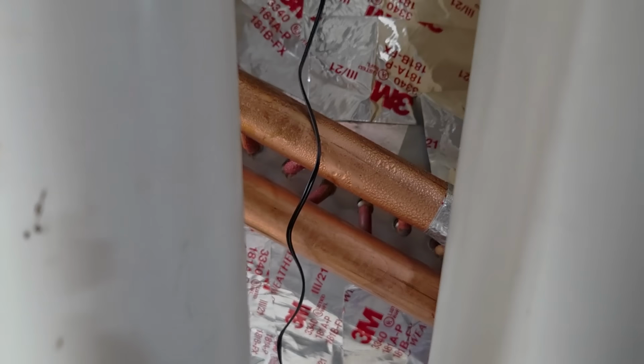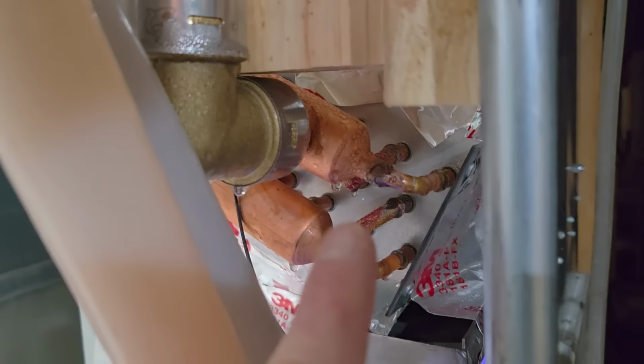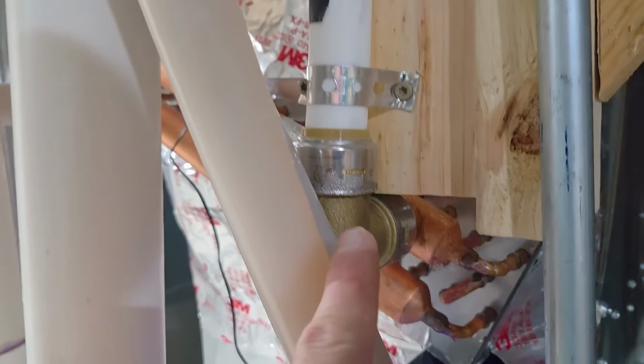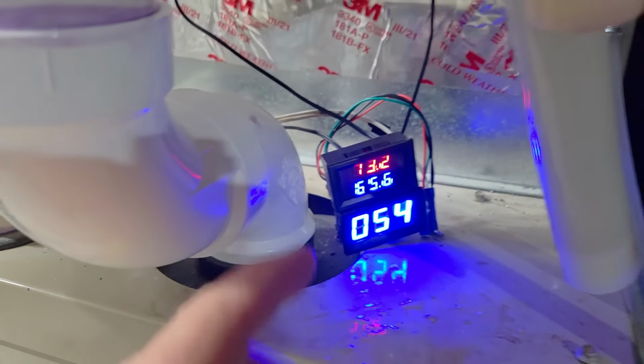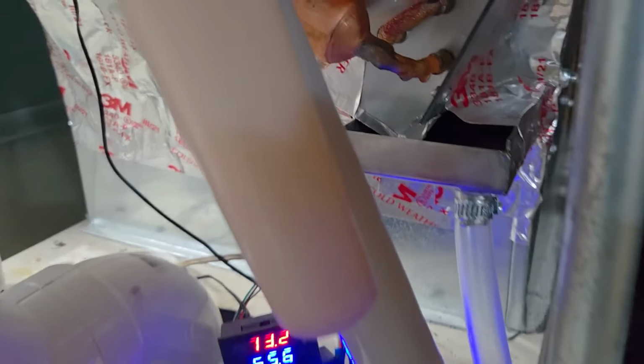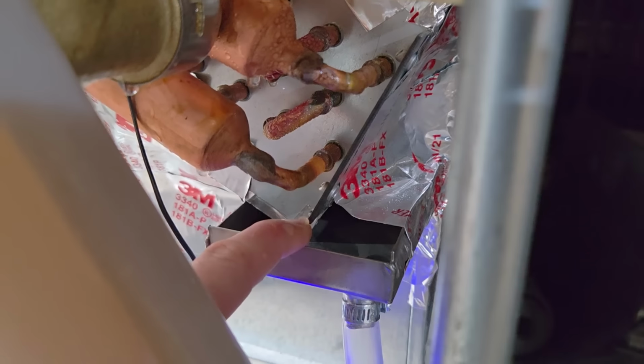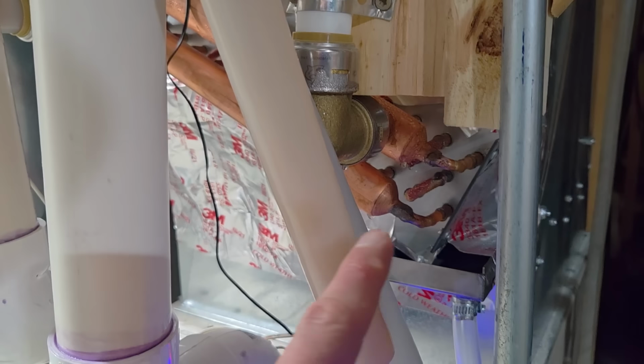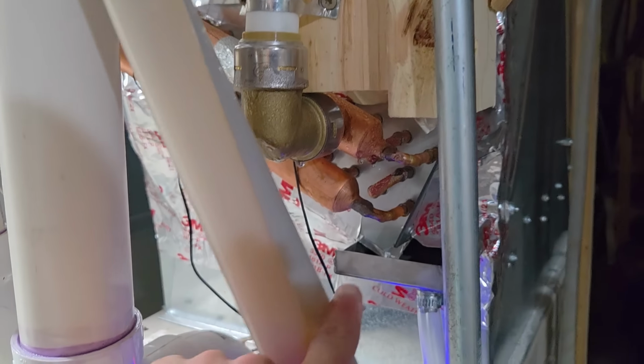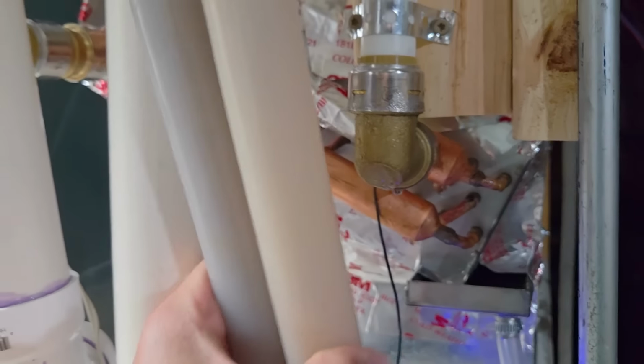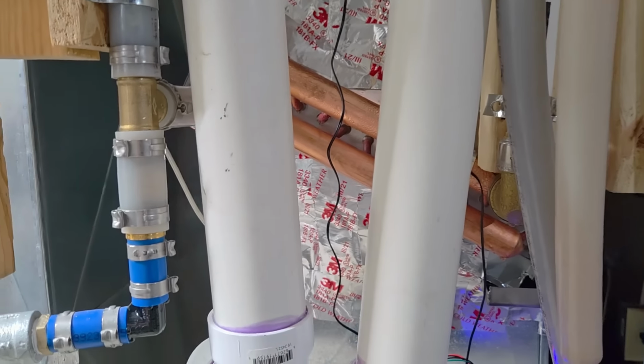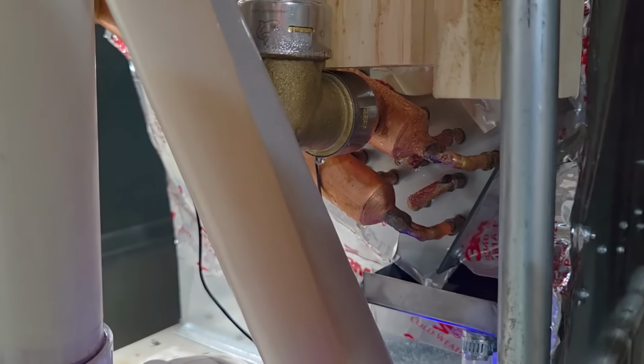And if we go over to the heat exchanger and the plenum of the furnace, we definitely have lots of condensation on the copper here. It's actually dripping off the end here and off these fittings and almost getting on my electronics. I don't see any running down the tube here. I'm guessing that the fan is drying it off before it has a chance to really run down and drip. The fact that these are running down and dripping on the end tells me that my heat exchanger, I think, is on enough of an angle for the water to collect at the end, if the water was cold enough for it to actually build condensation.